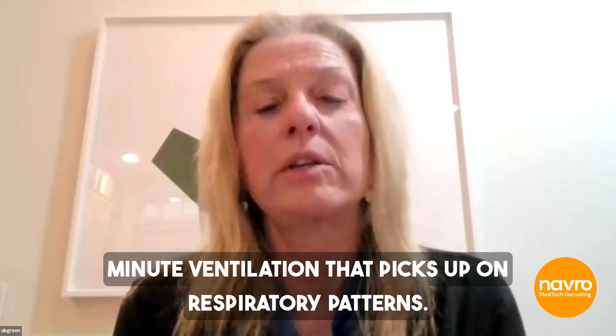Now the pacemaker, through a piezoelectric crystal in the generator, knows when the patient starts to be more active. There are other ways to sense activity. The piezoelectric crystal is called an accelerometer. There are other ways, and there's something called minute ventilation that picks up on respiratory patterns. So there are different types of devices. But the pacemaker now sees that the patient tries to do something. So now the patient is out walking the dog, and instead of having a heart rate of 45, this rate response mechanism kicks in and starts driving the heart rate up as if the patient had a normal heart rate response.